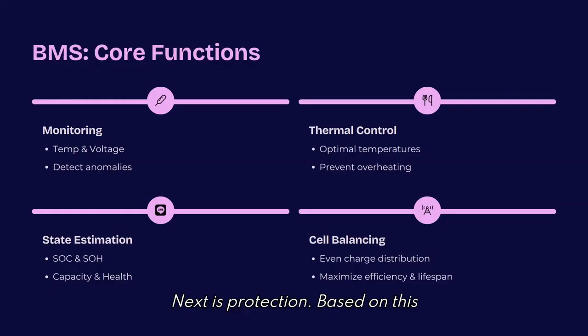Next is protection. Based on this monitoring, the BMS can take action. For example, if the current is too high during charging, it can open relays and stop charging. If the battery is overheating, it can switch on fans or liquid cooling. This is like having a guardian angel that reacts instantly when danger is near.